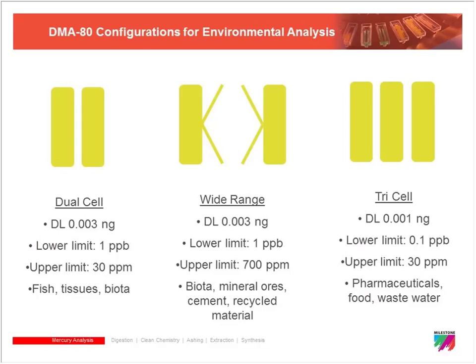For those that occasionally do wastewaters or samples with very, very low concentrations of mercury, we offer it in a tri-cell configuration, which contains the same 2 cells as the dual cell. However, we put another cell in the front end of the system to lower the detection limit to 0.001 nanograms, which puts its lower limit at 0.1 ppb. So it tags right along to the dual cell by an addition of a low limit cell.